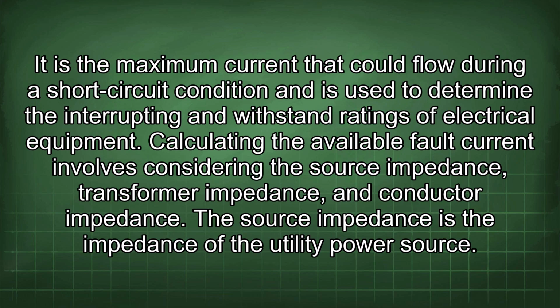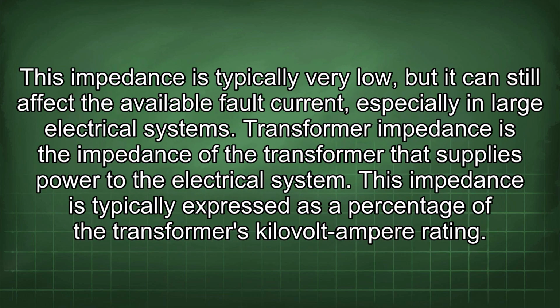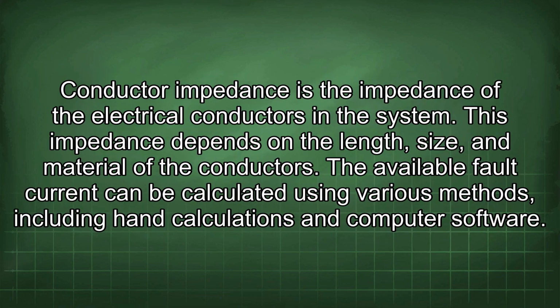Calculating the available fault current involves considering the source impedance, transformer impedance, and conductor impedance. The source impedance is the impedance of the utility power source. This impedance is typically very low, but it can still affect the available fault current, especially in large electrical systems. Transformer impedance is the impedance of the transformer that supplies power to the electrical system. This impedance is typically expressed as a percentage of the transformer's kilovolt-ampere rating. Conductor impedance is the impedance of the electrical conductors in the system. This impedance depends on the length, size, and material of the conductors.